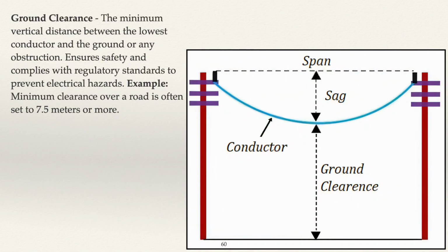Ground clearance. The minimum vertical distance between the lowest conductor and the ground or any obstruction. Ensures safety and complies with regulatory standards to prevent electrical hazards. Example, minimum clearance over a road is often set to 7.5 meters or more.